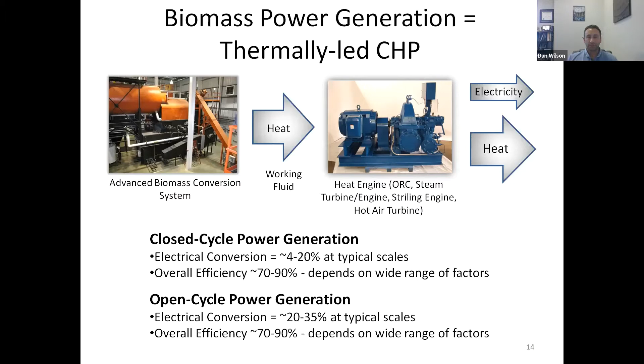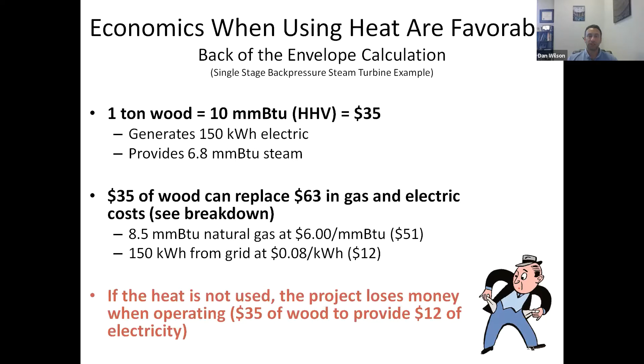This gives you the economics of a system similar to the one at the hospital we identified here. The basic gist is that for around 1 to 3 cents per kilowatt hour, depending on the price of wood you're purchasing, a back pressure steam turbine can provide power cost effectively. With thermal RECs, since that's such a big portion of the energy cost, if you're using wood chips as fuel you can offset a lot of the cost of that power, making it even less expensive than the 1 to 3 cents per kilowatt hour. We can't generate all a facility's needs, only what their thermal load dictates with this approach, but what we do generate is very cost effective and extremely efficient.